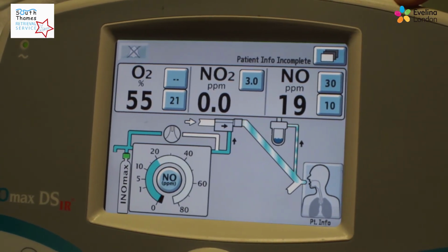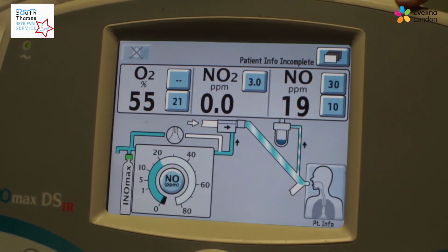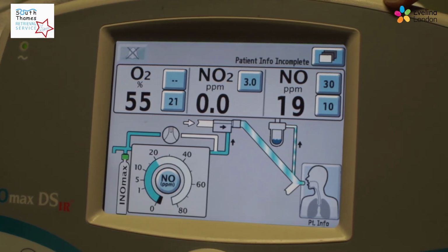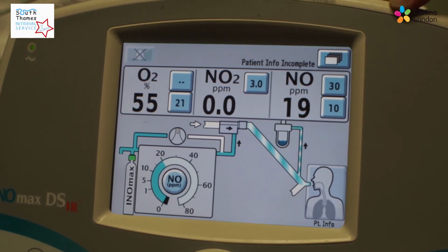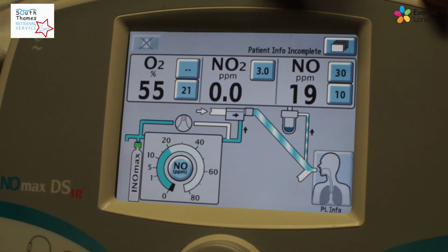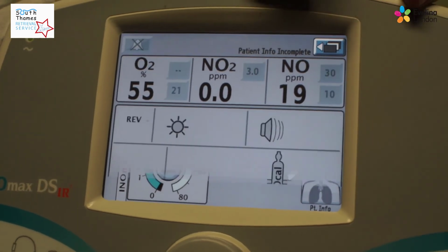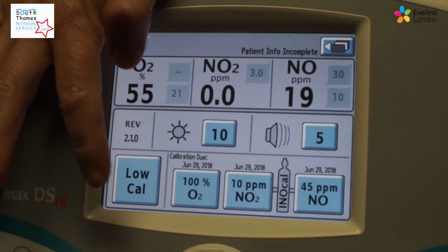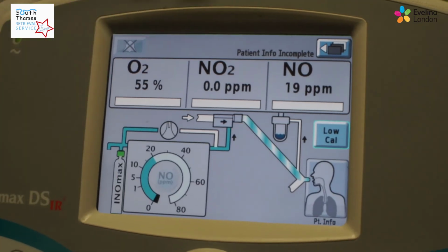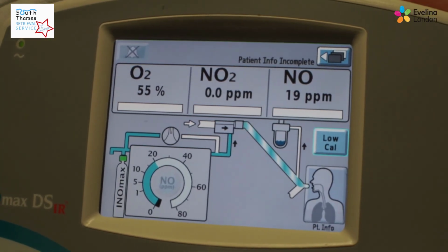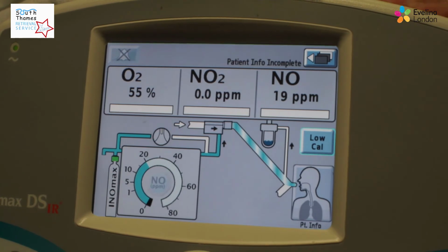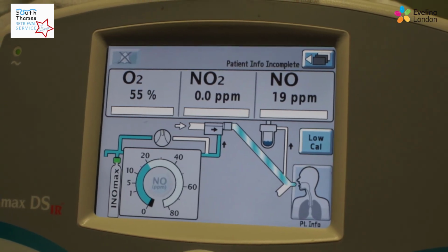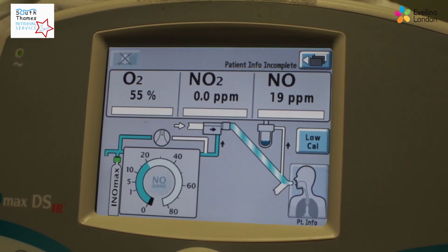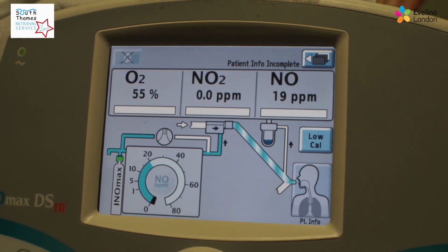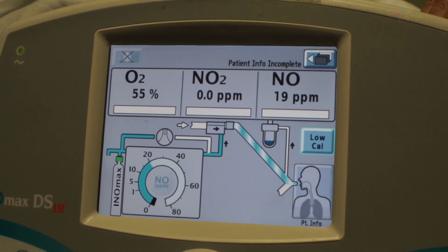It's really important, if your journey's been more than 20 minutes, to re-purge the old nitric from the tubing, as this is poisonous. You now need to calibrate the monitor by pressing this button and doing a low-cal calibration. This takes a minute to do. It's just important to know that these small nitric cylinders have 800 parts per million of nitric, which is the same as the large cylinders, so will last a long time. And you've also got a 6-hour battery life on your monitor.